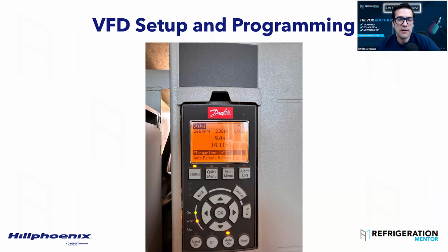A lot of people are afraid of VFDs or setting up VFDs, or maybe not afraid, just intimidated because they've not worked on them much. You want to give a couple of tips? This is a Danfoss one, the one in this picture, a very popular one on compressor control. Do you want to talk about some of the main settings to check on a startup, just a verification check? Because I know there's a lot of parameters in them, but you don't have to go through the 6,000 parameters, or 1,000 parameters, or 500 parameters. What are the main ones they've got to go in and verify?